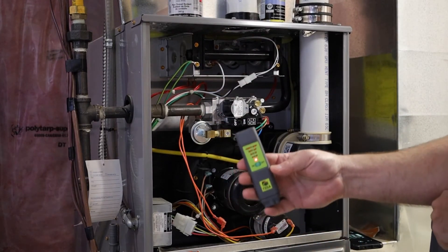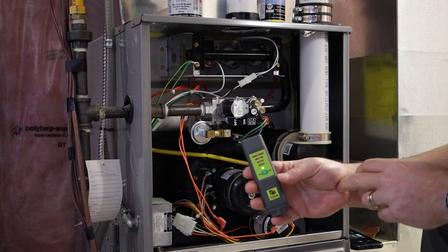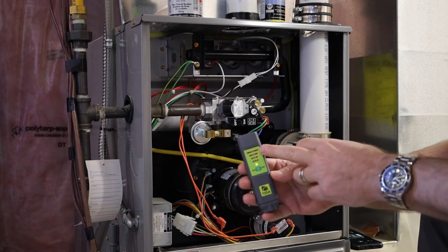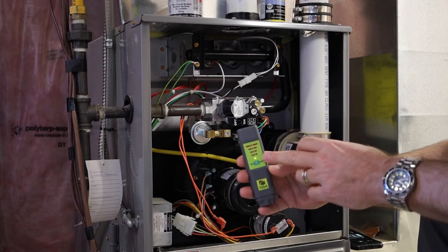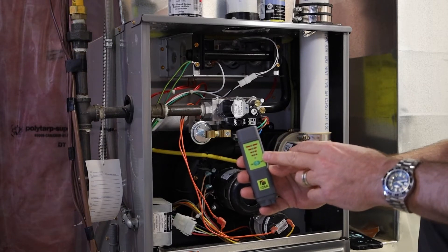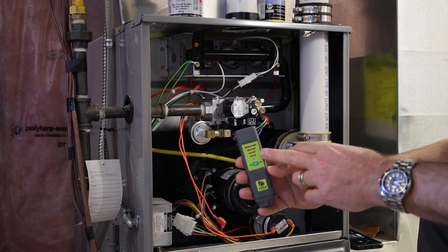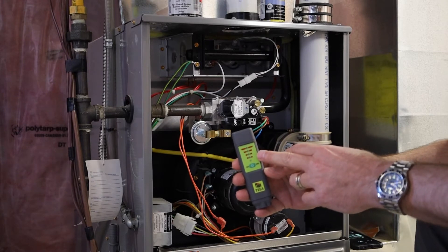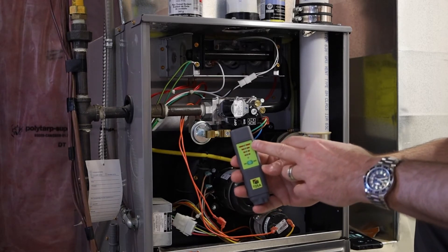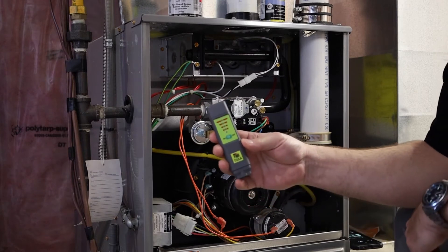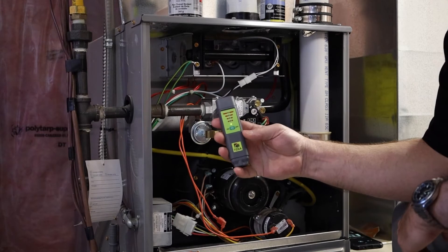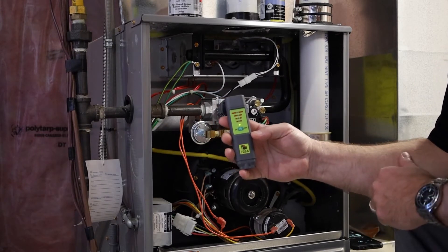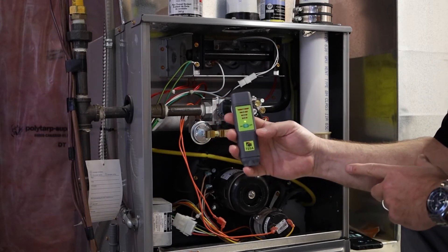So there it is, we're ready to go. There's indicating LED lights on here that indicate the size of the leak in parts per million. The first level would be under 500 ppm, then level two would be 1,000, 3,000, and then 5,000 ppm. So I'm just going to move this over towards my suspected leak and there it goes, very small leak so we're actually under 500 parts per million.